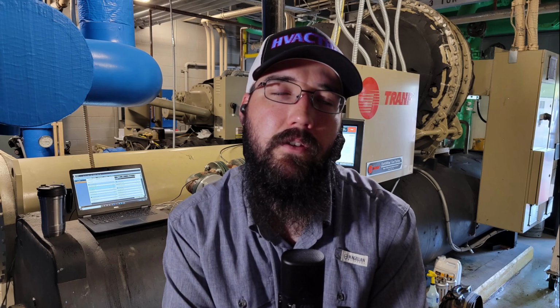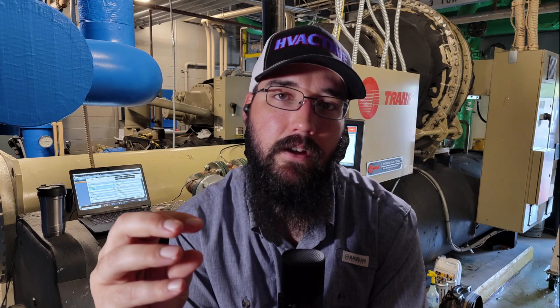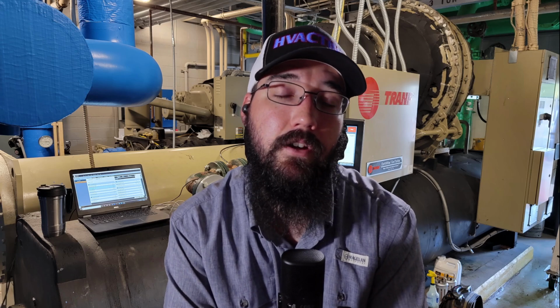But there's another symptom that comes alongside this when we get to that stage. When our threads start to get worn down, they typically start to bind a lot, because they're not making a proper fit between the threading and the shaft coming off the motor. Because we don't have a good fit there, they'll get in a bind frequently. And you can hear that. So for an EXV, if you have a lot of noise from that valve and it's making a really loud ticking sound the whole time it's trying to cycle, no matter what position it's in, that is evidence of a mechanical issue on that threading.